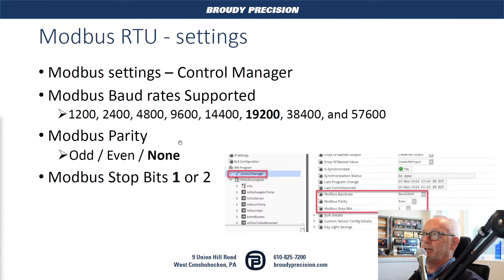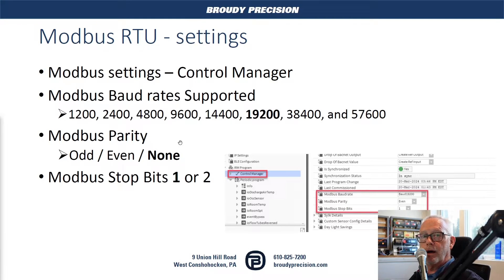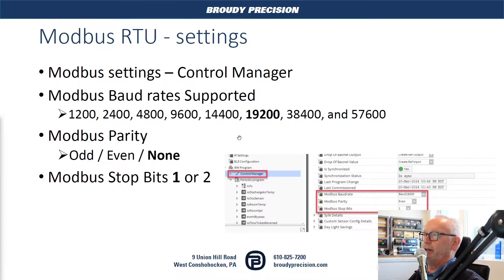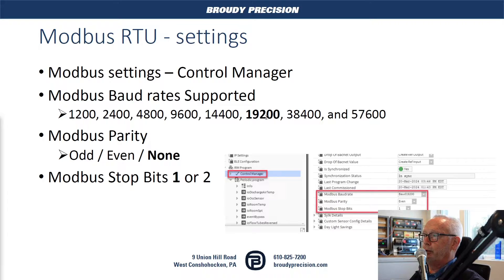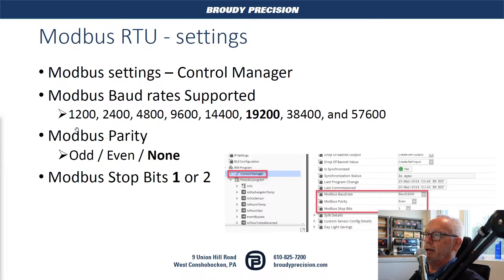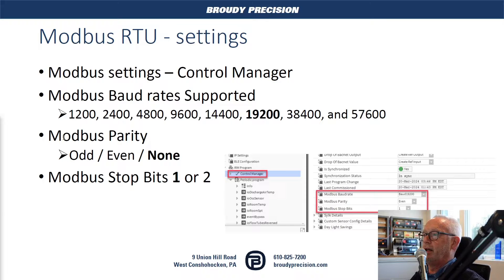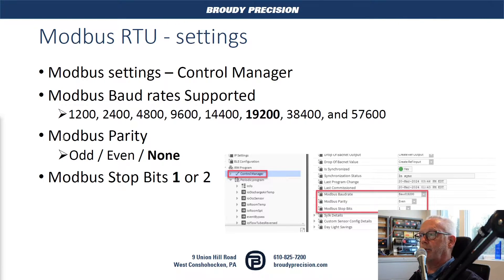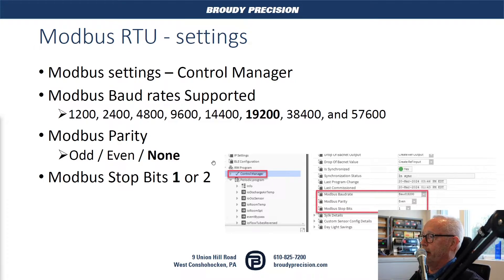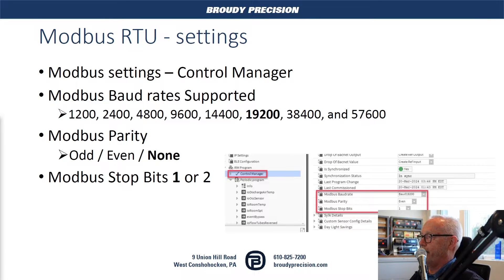The Modbus RTU settings you'll find underneath the control manager within the IRM program in the station and on each of the controllers. By default, the baud rate is set at 19.2, and you can see all the various baud rates available up to 57.6. You can choose the Modbus parity: odd, even, or none, none being the default. The Modbus stop bits would be either one or two, and the default is one.